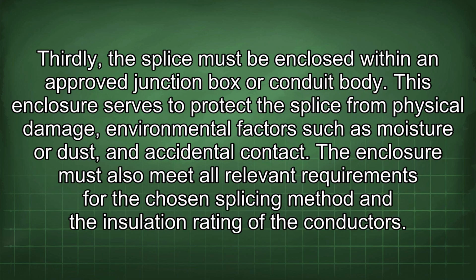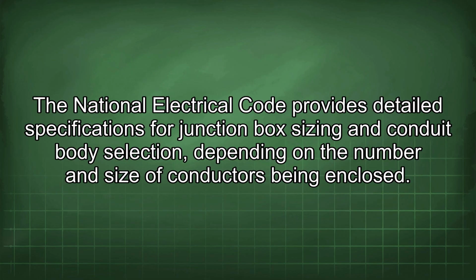Thirdly, the splice must be enclosed within an approved junction box or conduit body. This enclosure serves to protect the splice from physical damage, environmental factors such as moisture or dust, and accidental contact. The enclosure must also meet all relevant requirements for the chosen splicing method and the insulation rating of the conductors. The National Electrical Code provides detailed specifications for junction box sizing and conduit body selection, depending on the number and size of conductors being enclosed.